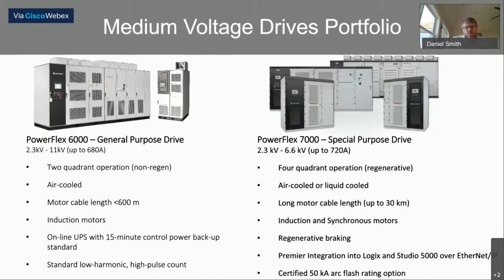So now what we're looking at is Rockwell's medium voltage drives platform, which is the PowerFlex 6000 and the PowerFlex 7000. The PowerFlex 6000 is Rockwell's newest offering in the medium voltage world. It is a cascaded H-bridge drive, meaning that it is voltage sourced and works very similarly to a low voltage drive. It has a phase shifting transformer on the front of it that gives it the low harmonics.